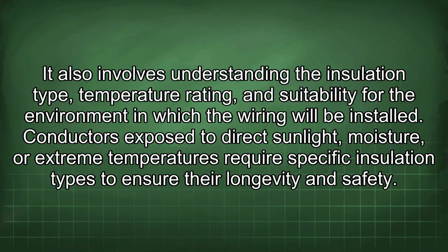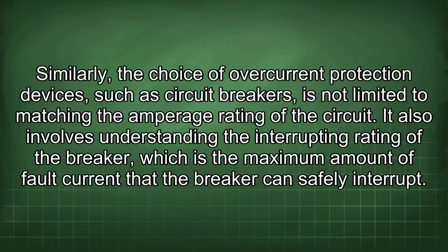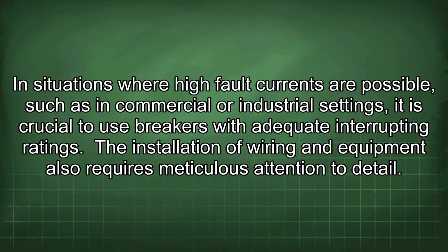Similarly, the choice of overcurrent protection devices, such as circuit breakers, is not limited to matching the amperage rating of the circuit. It also involves understanding the interrupting rating of the breaker, which is the maximum amount of fault current that the breaker can safely interrupt. In situations where high fault currents are possible, such as in commercial or industrial settings, it is crucial to use breakers with adequate interrupting ratings.